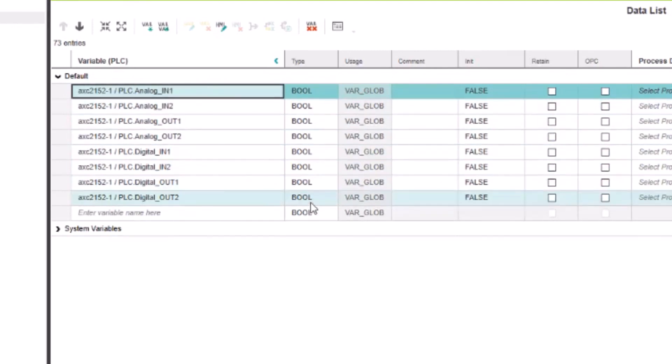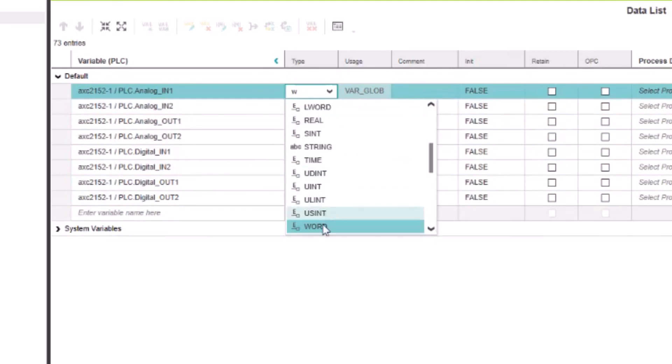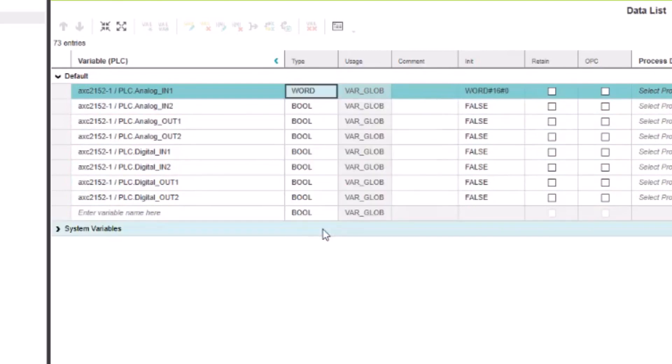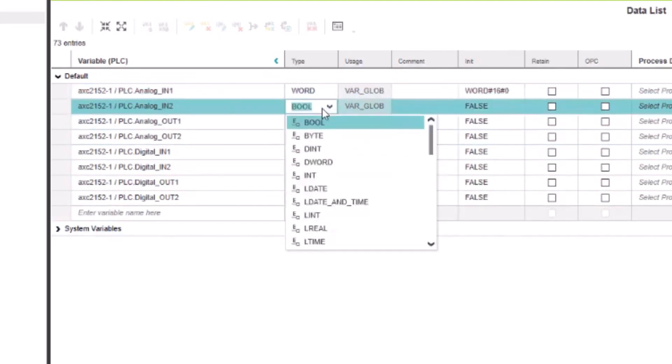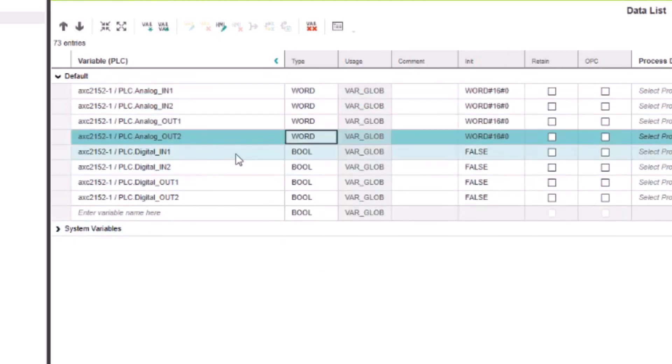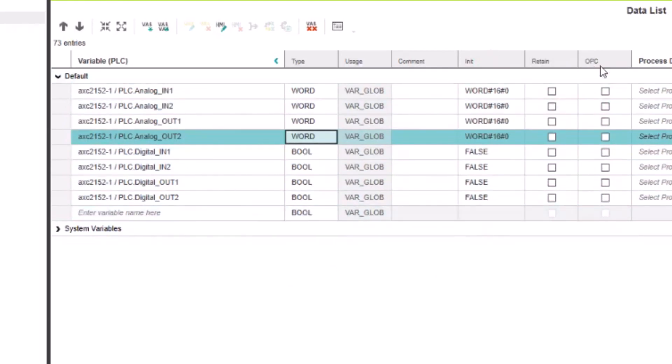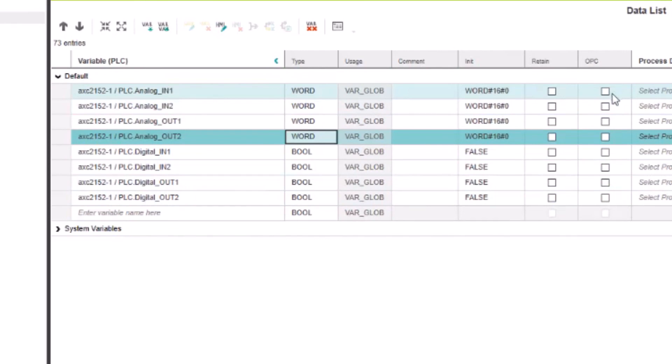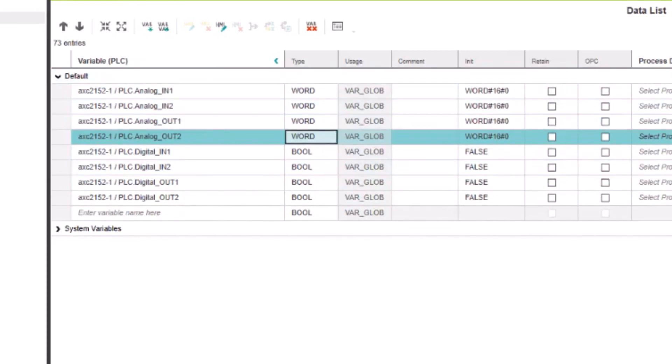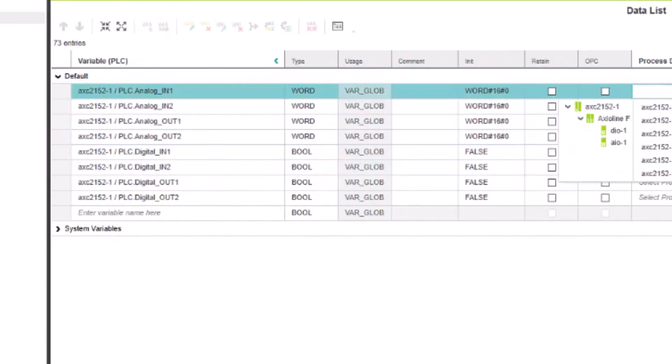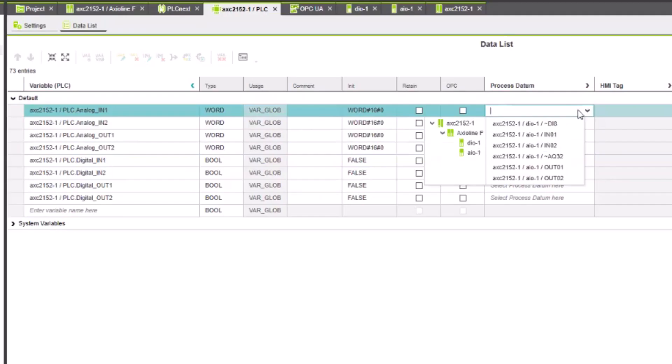So I've created two analog inputs, two analog outputs, two digital in and two digital out. They're all boolean right now, so we just go in here and we're going to change them to what we need. So we use word for the analogs and the digitals are all boolean, of course. So we'll leave those. We don't need to set OPC on or off because we've got the configuration set to all, which means it's going to pick these up anyway. And the next thing, so these are the variables for the PLC. That's effectively for internal. For the process datums, we can now pick the matching physical IO that we want for these.